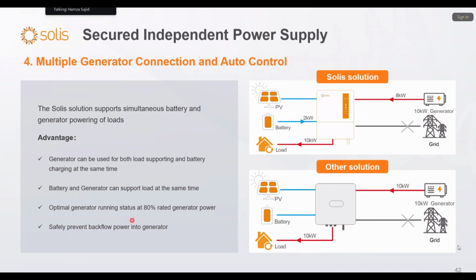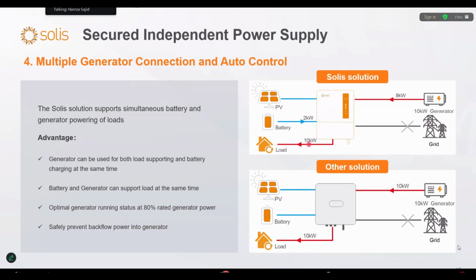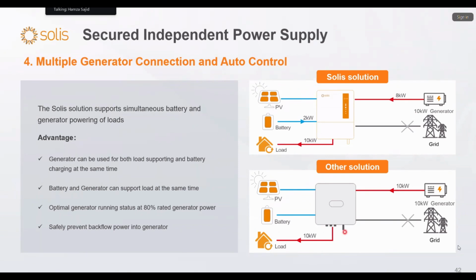Safely prevent backflow to the generator, because if you connect an on-grid inverter directly with the generator, there is a chance the inverter will turn on, create more power and export it back to the generator, and the generator can be damaged. So if you install the generator at the gen port, you make sure there is no power flowing back into the generator. Other brands don't have this solution. Like if the 10 kilowatt is available, it is going to support the load directly. So together the battery cannot support the load in this case. You can see.